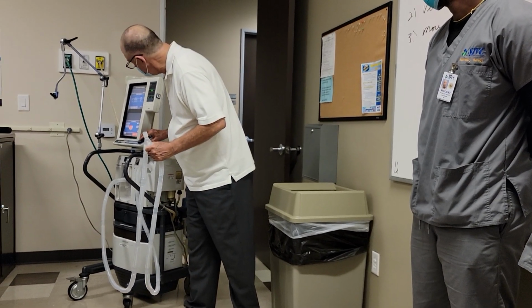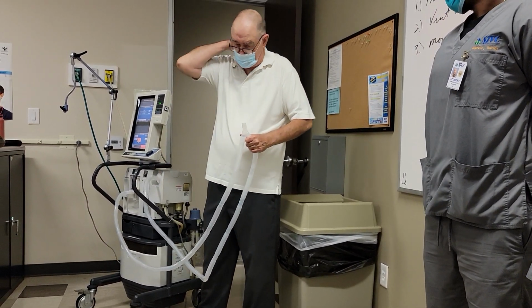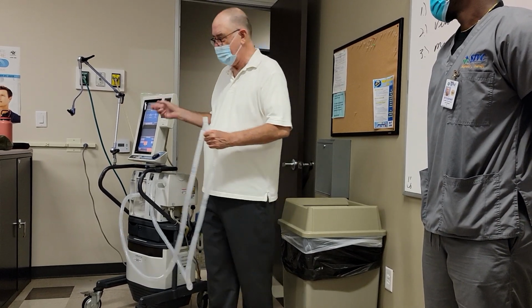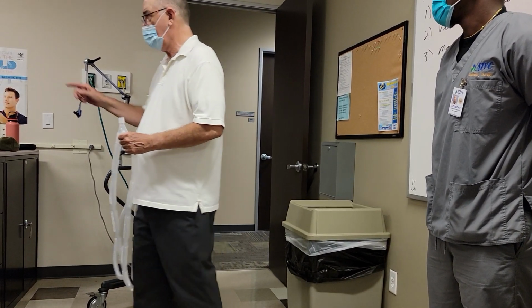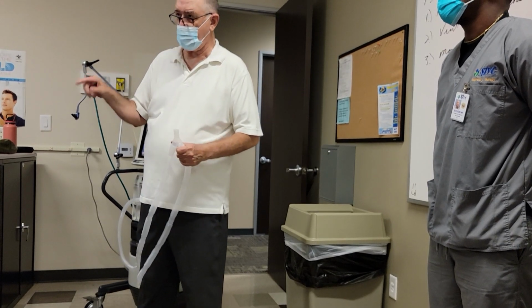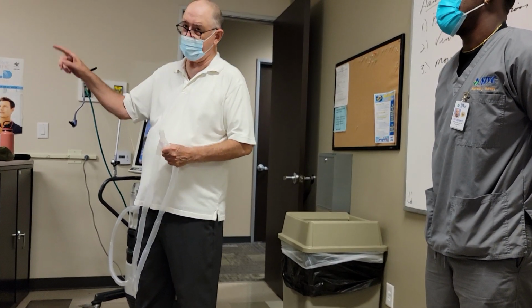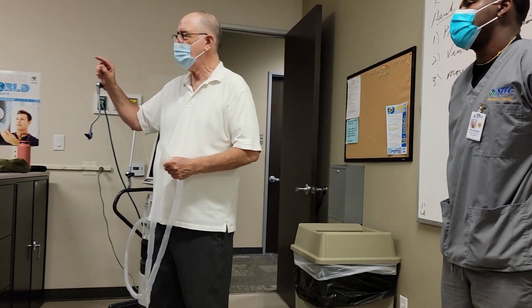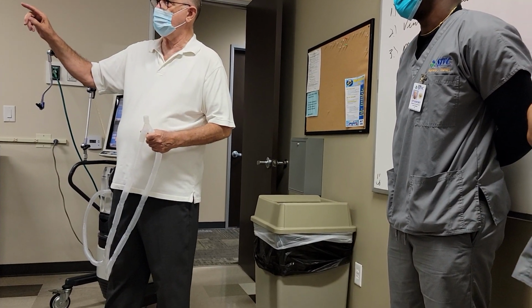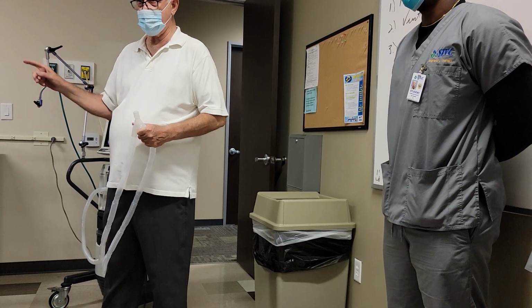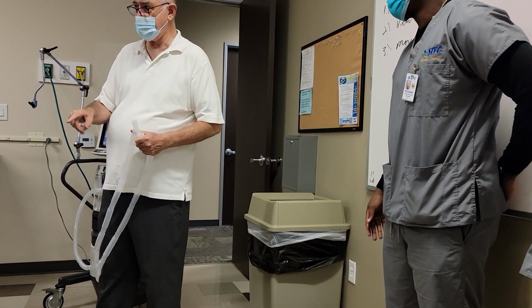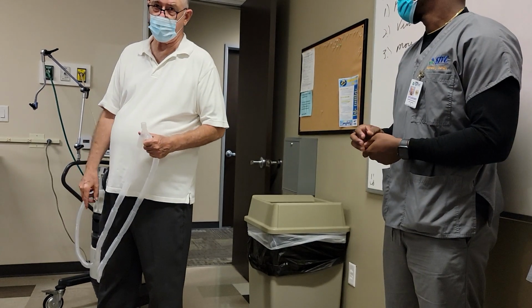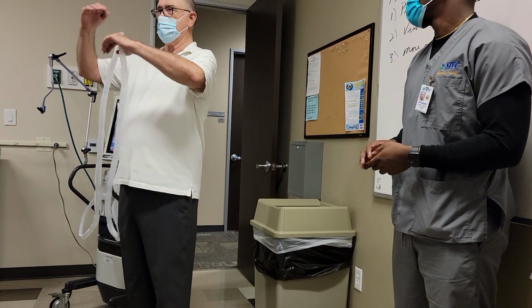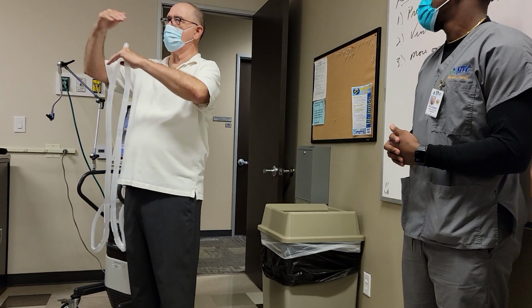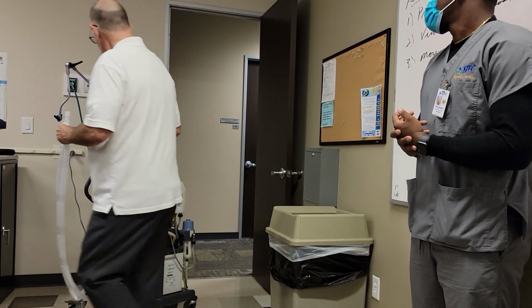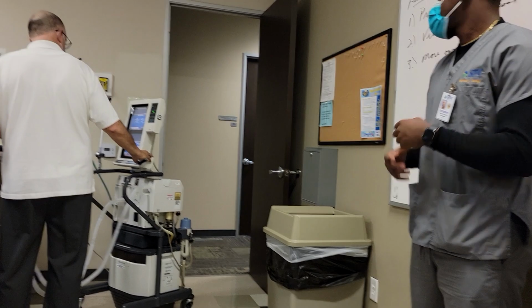Then there's another mode called VC+. And this is another one of those problems where this machine says it's VC+. That machine back there says it's pressure regulated volume control. And I will tell you right now that that's a lie, it's not volume control. But it's an advanced mode. If you don't understand volume control and you don't understand pressure control, you'll never understand VC+. So I'm trying to get you guys to understand the order of things. Okay, so we're going to go back to volume control.